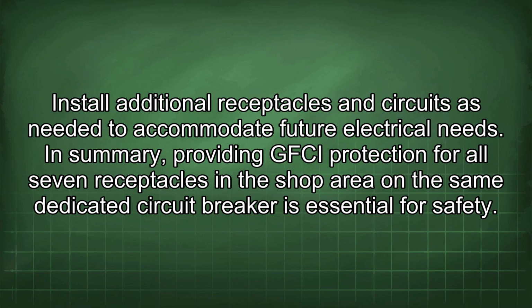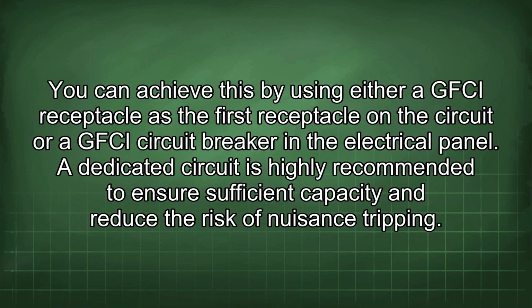In summary, providing GFCI protection for all 7 receptacles in the shop area on the same dedicated circuit breaker is essential for safety. You can achieve this by using either a GFCI receptacle as the first receptacle on the circuit or a GFCI circuit breaker in the electrical panel. A dedicated circuit is highly recommended to ensure sufficient capacity and reduce the risk of nuisance tripping.